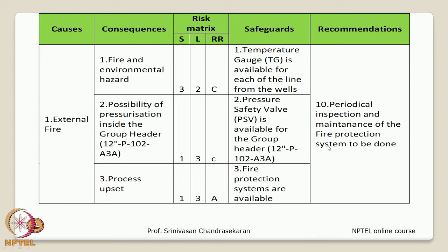So, always put a safety recommendation here that they should be periodically inspected and maintained, and there should be a record available in the system of when they were last serviced, when they were last maintained, and at what pressure, temperature and operating condition they were tested. That should be available for inspection, and based on that you will recommend that periodic inspection is still necessary, so that such serious hazards can be easily controlled if these are in place and also working. So, you have to ensure that. HAZOP reports also take care of periodic maintenance. That is very important.